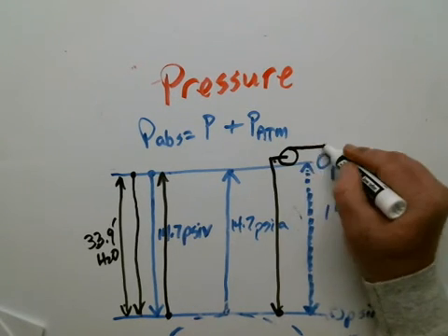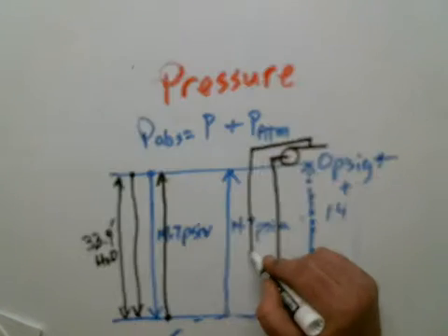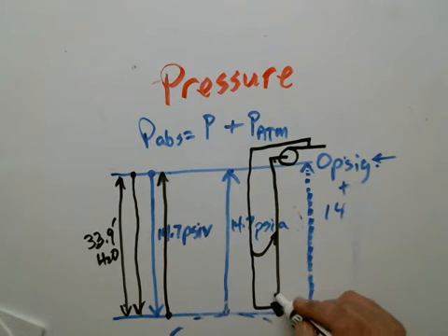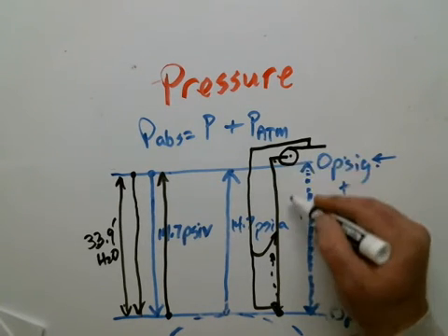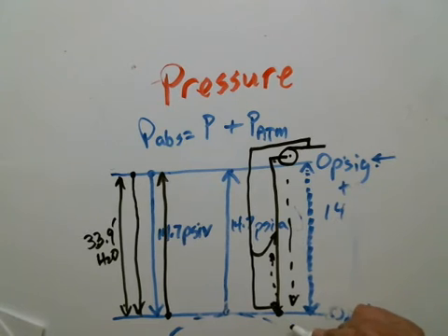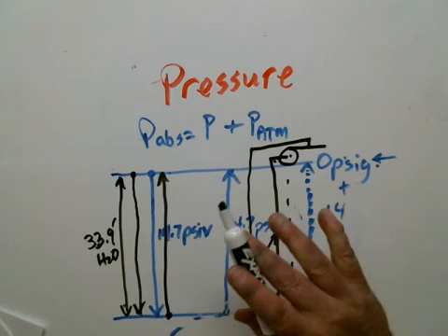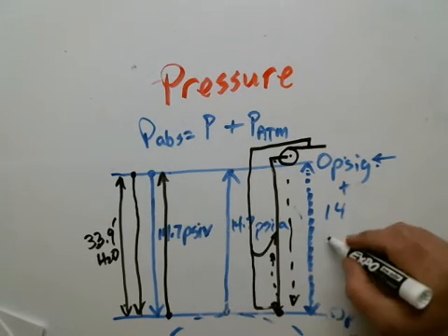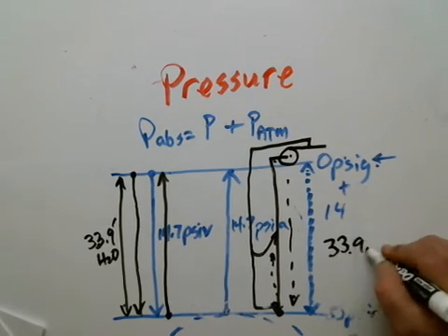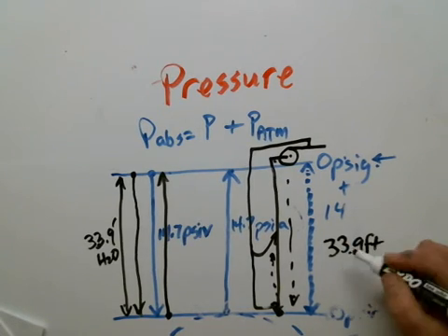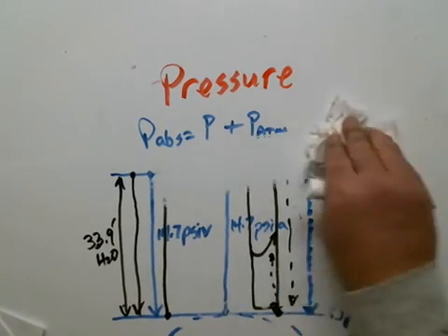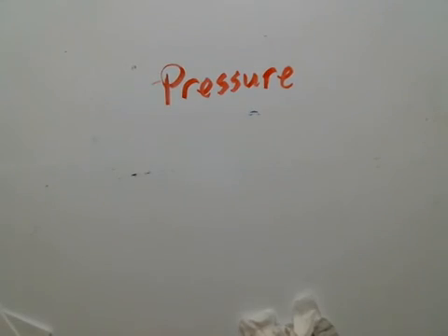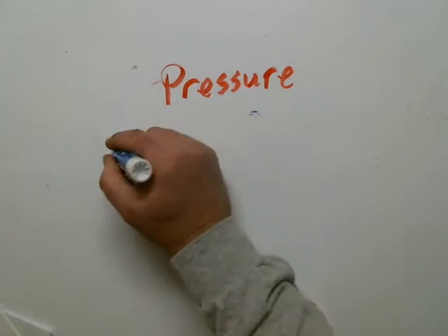I would have to take the discharge and either create a jet pump arrangement or push the water up or lower the pump down here. So the best pump in the world can only create a perfect vacuum. The best pump in the world can only lift water 33.9 feet. You've got to do something else. There's other ways to express this. If we can do feet of water, therefore we can do it in inches of water. It's pretty cool. So this is misunderstood all the time.